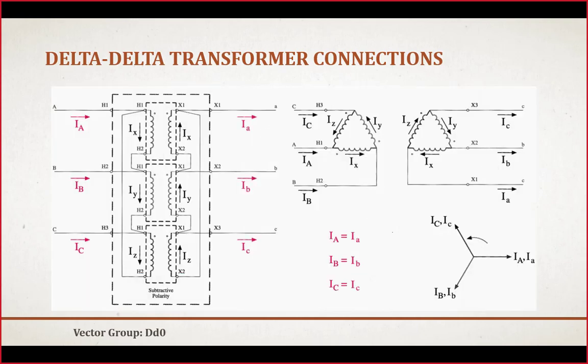So here we have used the two side windings to make a delta, and the delta has been made in such a way that both deltas are similar to each other. Here, if we look at this first winding, we have connected this dotted end H1 with the non-dotted end of the last winding H2. Now the same is the configuration of the delta on the other side, the low voltage side. Here we can see deltas are connected on the low voltage side in the same configuration.